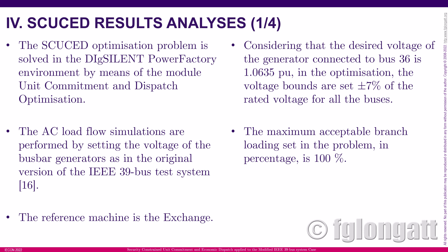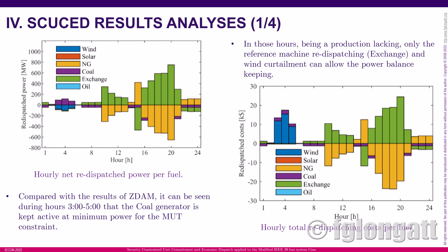For the second stage results — the SCUCED — we are using the powerful tool from DIgSILENT PowerFactory. PowerFactory has a very useful tool for unit commitment and economic dispatch, and we are leveraging that to solve the second stage. We are considering voltage limits and power capacity at the branches. On the left-hand side, you can see the hourly redispatch power per fuel, and the most important balancing generation technology is natural gas, also including the exchange from the external grid.